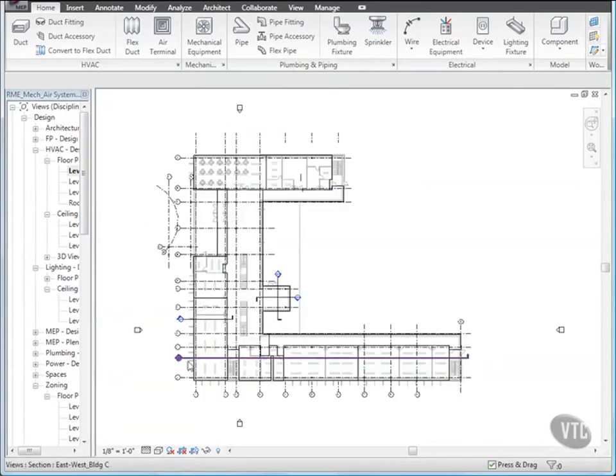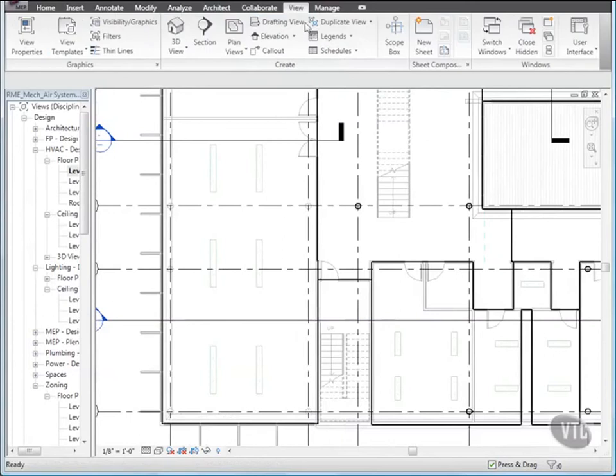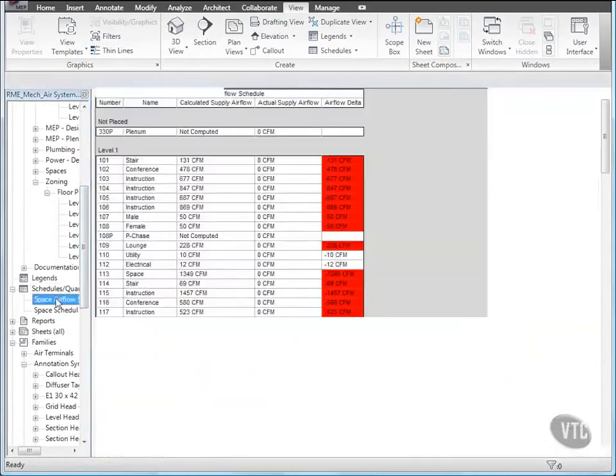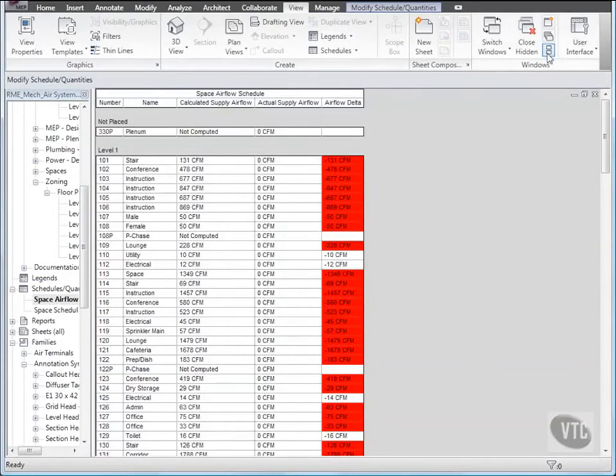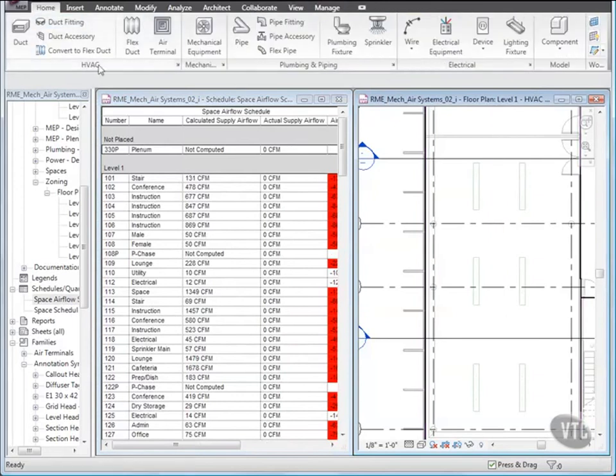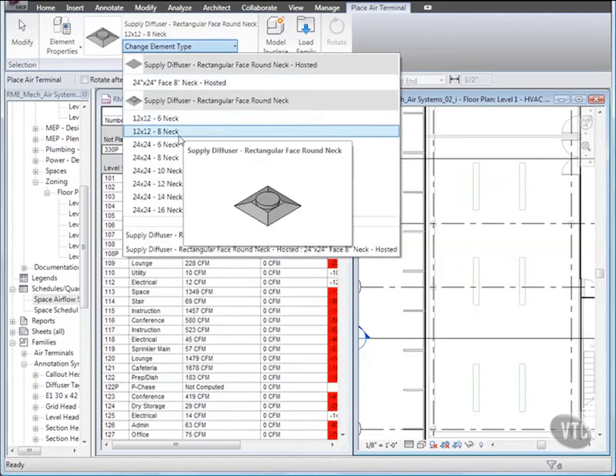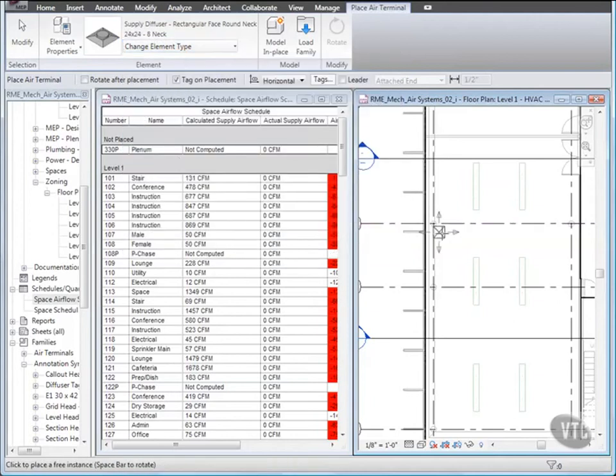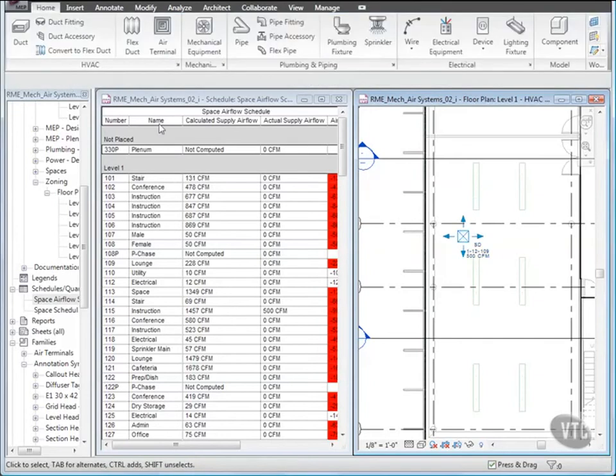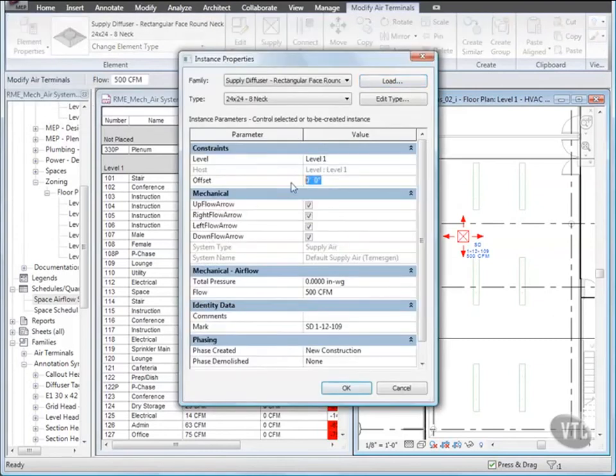And zoom in to the lower left corner of the building. Then from the View Tab's Windows Panel, click Close Hidden, and then open the Schedule View, Space Airflow Schedule, and then go back to the View Tab and click Tile Windows. Then make the Floor Plan active, and from the Home Tab, click Air Terminal. Then click Change Element Type and select 24 by 24, 8 neck, and place the Air Terminal in the space as shown, and click Modify. Then select the Diffuser, go to its Instance Properties, and for Offset, enter 8 feet, and change the Flow to 360 CFM, and click OK.